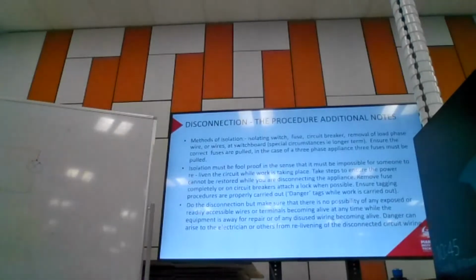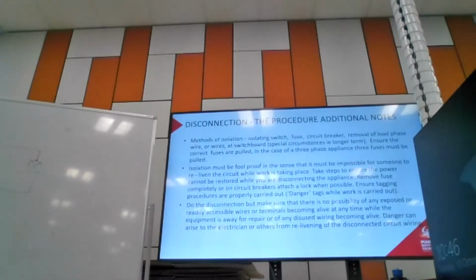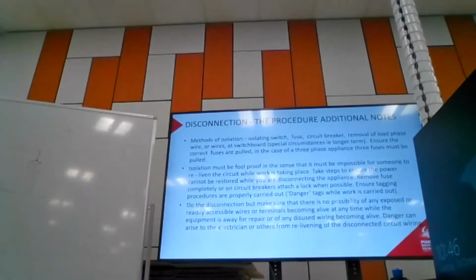Isolation must be foolproof in the sense that it must be impossible for someone to reliven the circuit while work is taking place. Take steps to ensure the power cannot be restored while you are disconnecting the appliance. Remove the fuse completely, or on circuit breakers attach a lock where possible. Ensure tagging procedures are properly carried out - danger tags while work is carried out, etc.